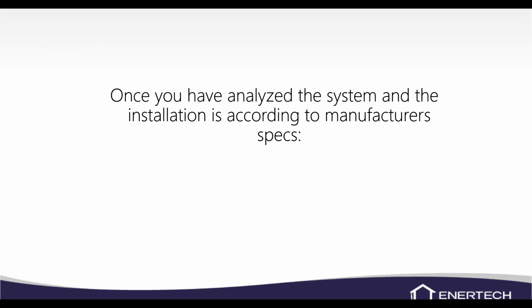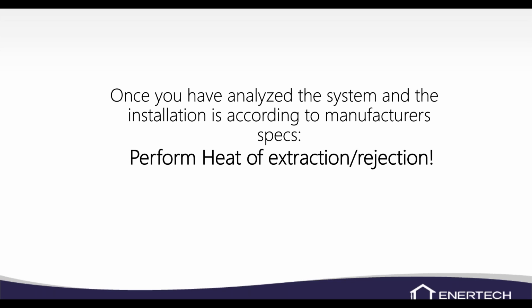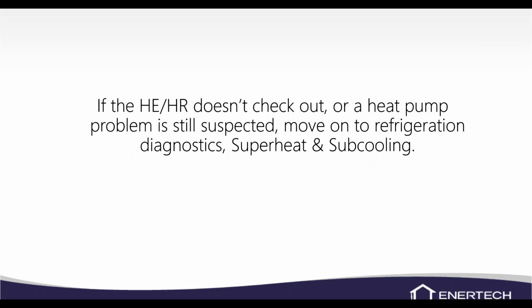Once the system has been analyzed and the installation checked according to manufacturer specs, perform the heat of extraction, heat of rejection. When you do heat of extraction or heat of rejection, we're going to establish flow, and then we can also see our temperature difference. So heat of extraction, heat of rejection, we have our own webinar on it. So if you're not real sure how to do that, check out our YouTube channel, or I try to do a heat of extraction rejection webinar once a month because it's that important. It's such a good diagnostic tool as long as you have the IOM, but always perform the heat of extraction or rejection first. If the heat of extraction and rejection doesn't check out, or the heat pump problem is still suspected, then we'll go ahead and move on to refrigerant diagnostics. We'll check your superheat and your subcooling.